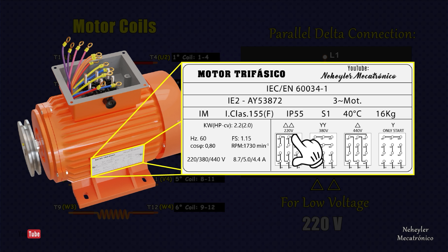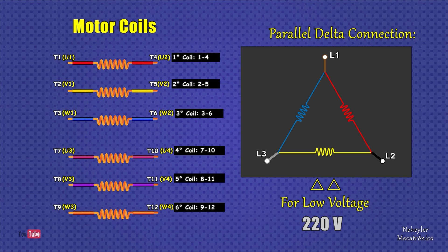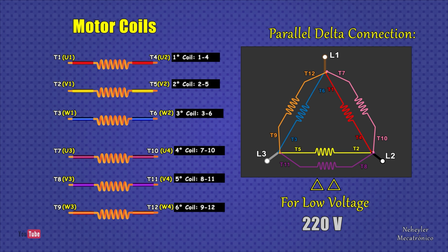Now let's look at the parallel delta or double triangle configuration. This configuration is used for low three-phase voltage. First, a triangle is formed with three coils. Reading the terminals clockwise: terminals 1 and 4 correspond to the first coil, 2 and 5 to the second coil, 3 and 6 to the third coil. The other three remaining coils are placed in parallel on each side of the triangle: terminals 7 and 10 parallel to the first coil, 8 and 11 parallel to the second coil, 9 and 12 parallel to the third coil. The three power cables exit from each vertex of the triangle.